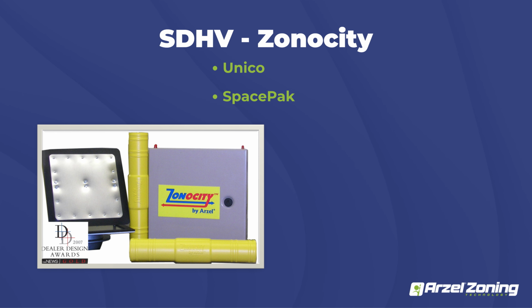So this is going to be small duct high velocity zoning. It's either going to use our MPS panel or it's going to be our HeatPumPro panel, depending on if it's single stage or two stage small duct high velocity. But we are compatible with it. We can zone those pieces of equipment as well. The biggest thing to keep in mind if you guys are going to do a job with a Spacepak or Unico, small duct high velocity in general, is making sure that the equipment has enough runs when it was pre-installed. So before the zoning is installed, you just need to make sure you have enough outlets per ton as designed by the manufacturer. As long as you have that, you can definitely zone it. There are some limitations on how many zones you can do. If you guys ever need anything like that, we can email you the guidelines as well, so you can get an idea of what you're going to end up doing.